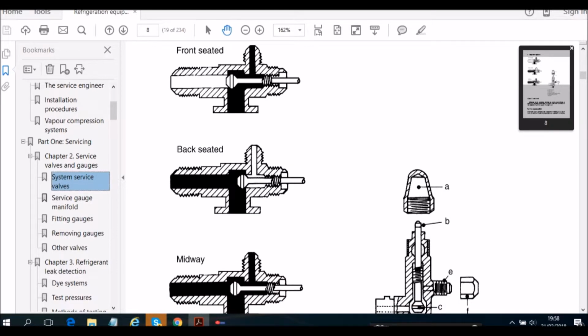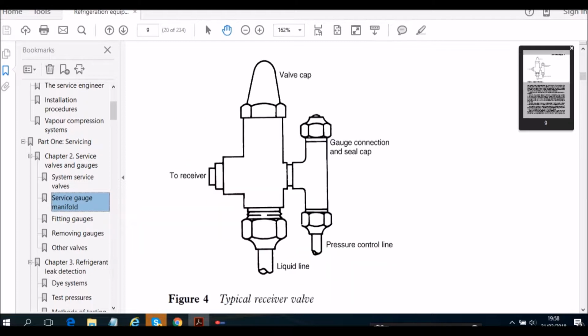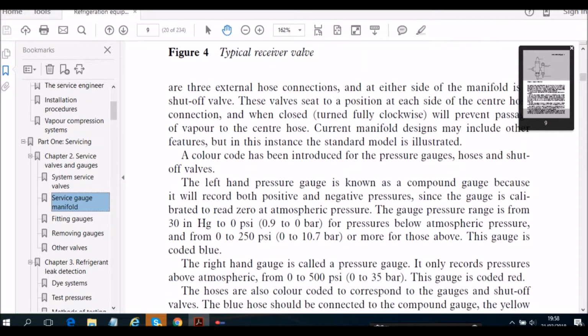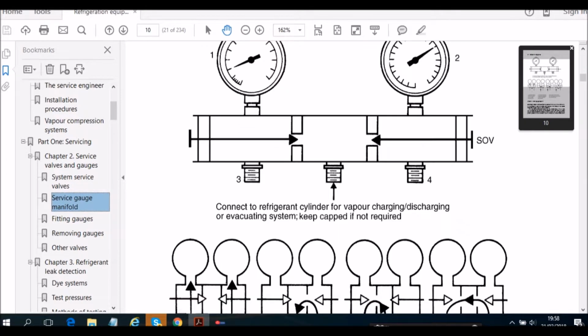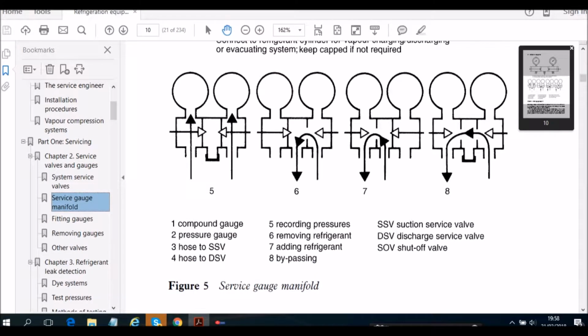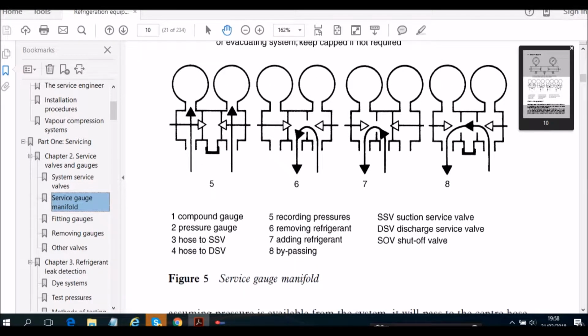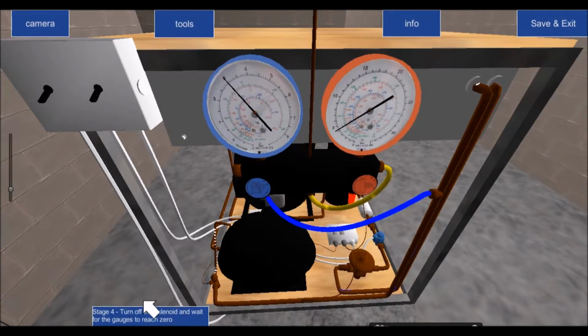Therefore, this hose line is only under pressure because of the actual gauges themselves. The only reason it's under pressure is because the gauges are allowing whatever was in the high side hose access to whatever's in the low side of the system. So basically we're in this scenario here. The pressures have equalized across here and no new refrigerant is coming in because of our back-seated position. It says turn off the solenoid and wait for the gauges to reach 0.